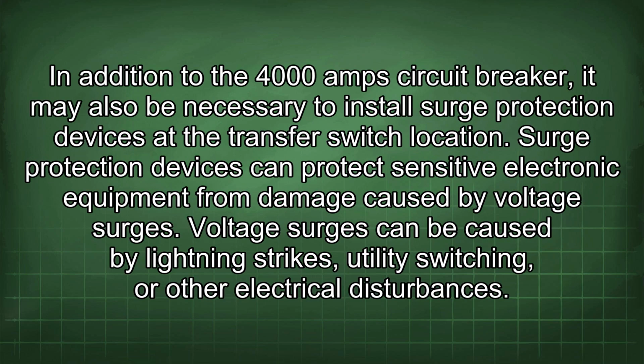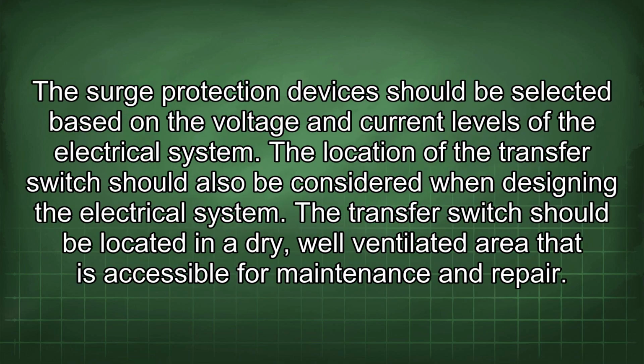In addition to the 4000 amp circuit breaker, it may also be necessary to install surge protection devices at the transfer switch location. Surge protection devices can protect sensitive electronic equipment from damage caused by voltage surges. Voltage surges can be caused by lightning strikes, utility switching, or other electrical disturbances. The surge protection devices should be selected based on the voltage and current levels of the electrical system.